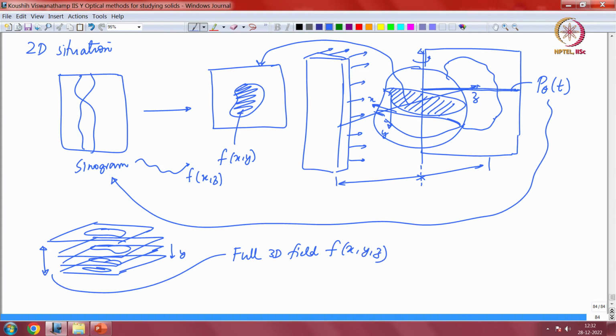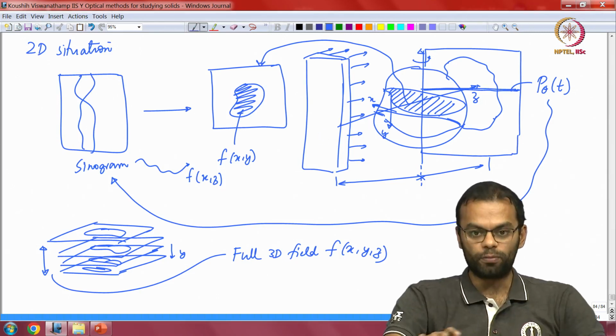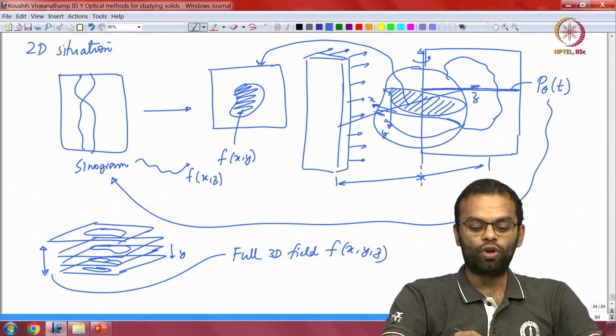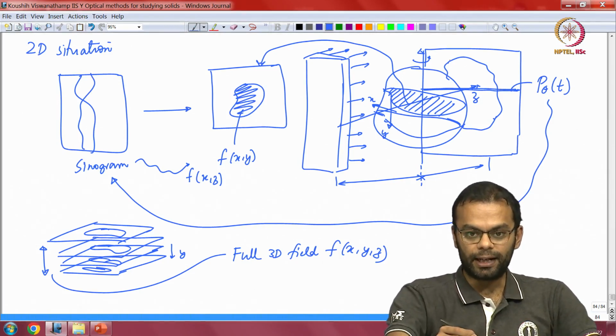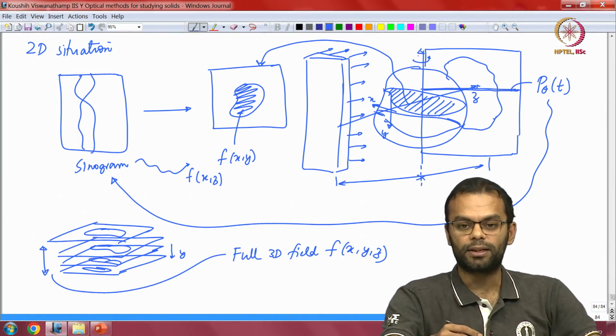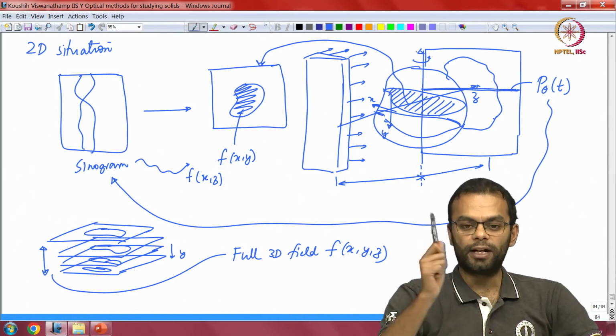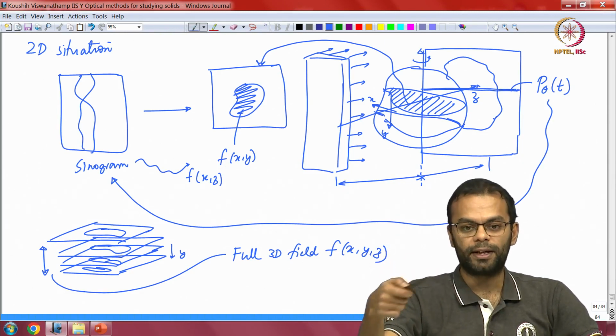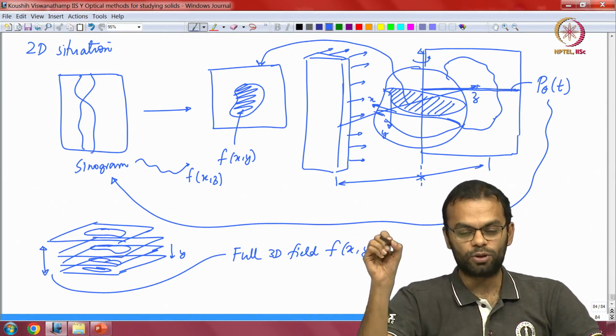Okay, and that is typically how, well, it is not typically how it is done, but conceptually that is how it is done. Typically what will happen in a practical situation is you will not have a big tube-light type of source making X-rays, because that almost certainly never happens. You will have a point source, and it will not generate parallel rays, it will generate a cone beam, what is called a cone beam, right. And when you have a cone beam you will start seeing parallax essentially, because some beams will go slightly larger distance compared to others. So when you rotate you will not get parallel information, but you will get information depending on the angle with respect to the source position.